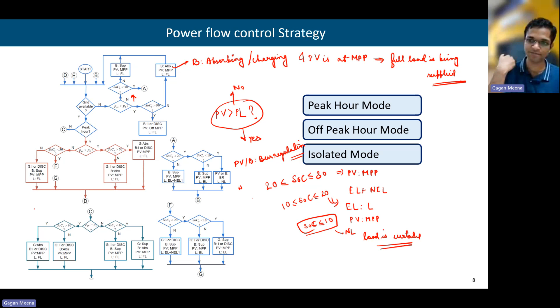The battery will be idle because it is already fully charged up to 90%. We cannot charge the battery more than 90%. That will result in overcharging, and we want to avoid overcharging and deep discharging. We have already discussed here that we want to reduce the stress on the battery, and for that we need to avoid overcharging and any kind of deep discharging. That is very important to increase the lifespan of the energy storage. That's why if the SOC is more than 90%, we will not charge the battery. The battery will be idle, and the excess generation from the PV will go into the grid, and the grid will be absorbing. PV will be acting at a maximum power point. The load will be supplied, the battery is disconnected, and the grid is absorbing.